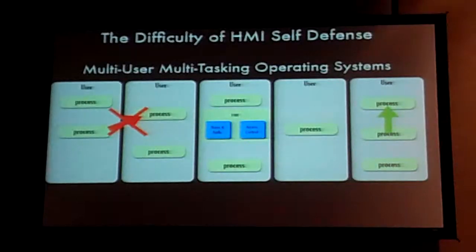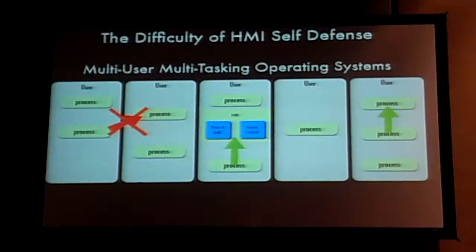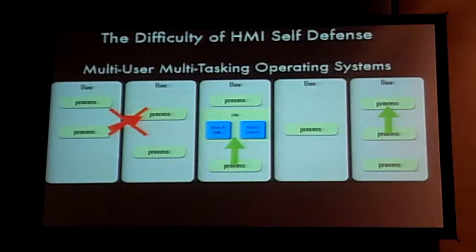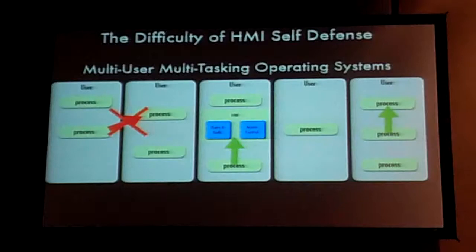The problem is if you have your HMI running as the user that's currently logged in, you'd better be protecting them from bouncing out of that interface. Because if they can ever get out of it, or if they can ever find some other way of running code — USB, FireWire, anything like that — then it's over. You've not only got access to the files associated with that HMI, but you can also monkey around with the software.